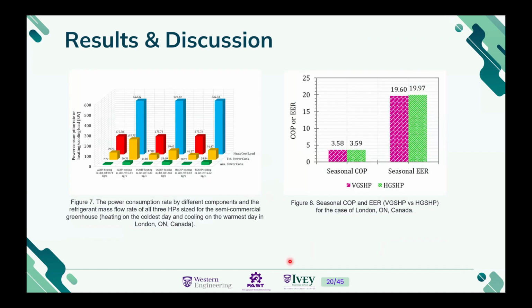Here we evaluate the performance of our heat pump components. Looking at figure 7, the total power consumption of the compressor for the air source heat pump was considerably higher than for ground source heat pumps, in both heating and cooling modes at the same demand level. This is the main reason the COP of the ground source heat pump is higher than that of the air source heat pump.